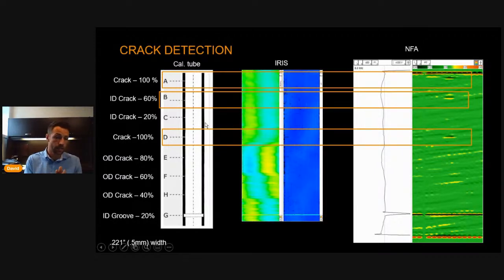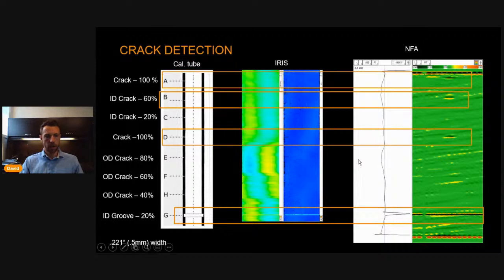Keep in mind that these are 0.5 millimeter width cracks, or 0.021 inch width. So these are very, very small. As for the OD cracks, as expected, we were not able to pick up any of those as they are outside and very small defects. But neither was IRIS capable of detecting those cracks. So we see that NFA really offers a lot more for crack detection compared to IRIS.